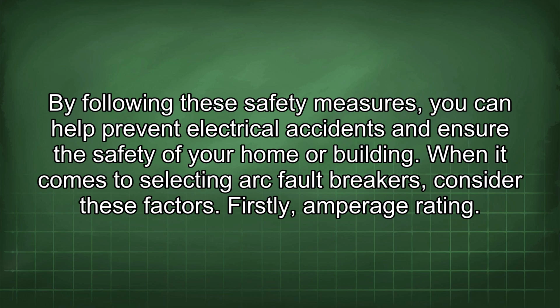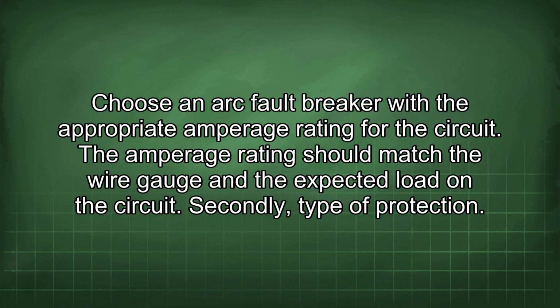Firstly, amperage rating. Choose an arc fault breaker with the appropriate amperage rating for the circuit. The amperage rating should match the wire gauge and the expected load in the circuit.